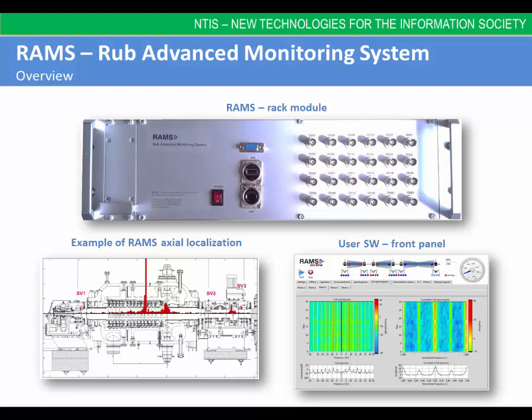The RAMS is an advanced diagnostic system — a high technology device capable of detecting the origin and occurrence of rotor-stator contact in real time, and in parallel very accurately determining the place where the contact occurs from standard signals of shaft displacement and stator vibration measured on steam turbines. The RAMS thus utilizes the standard range of installation of transducers for measurement of vibrations of steam turbines.